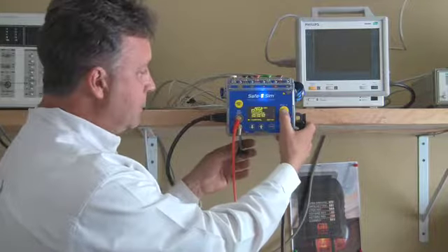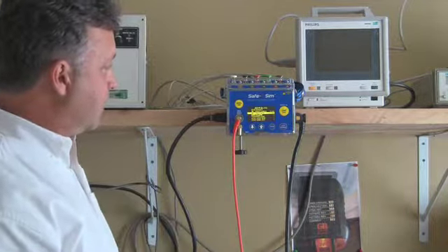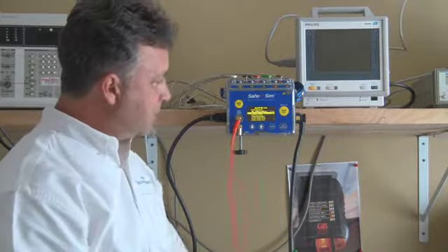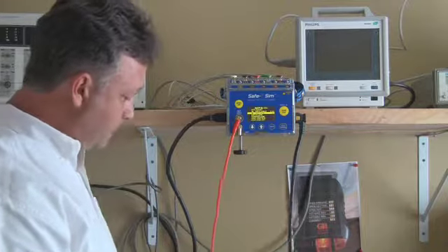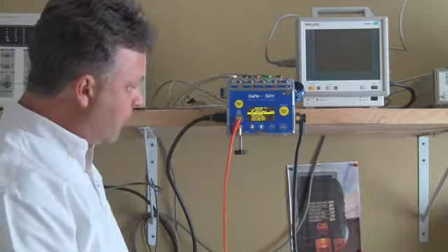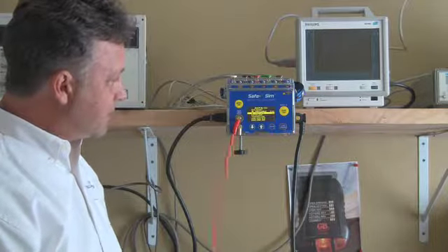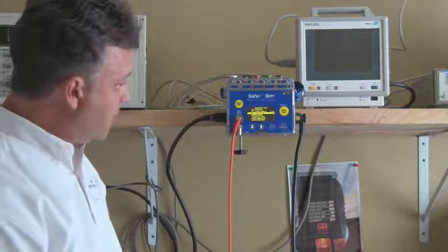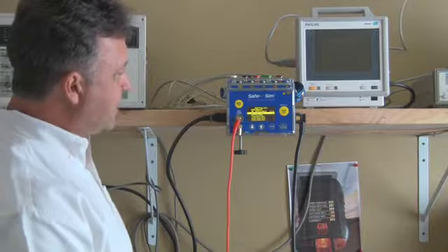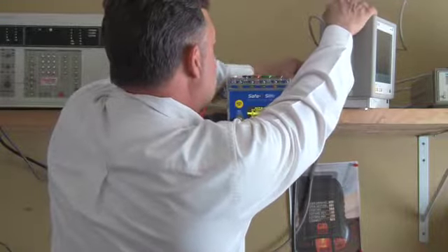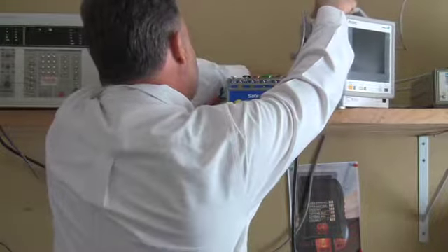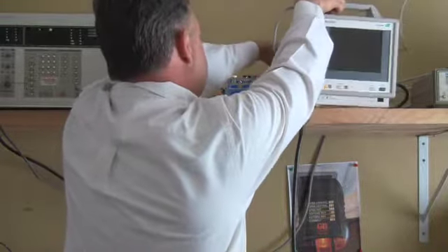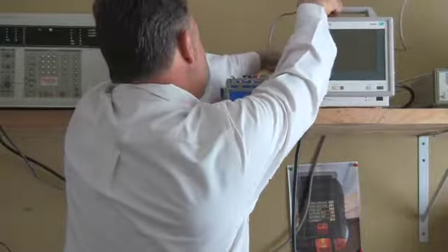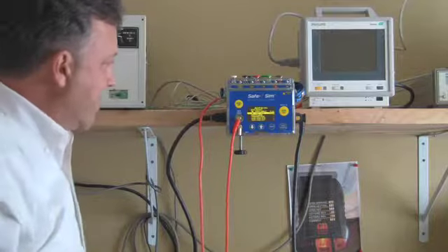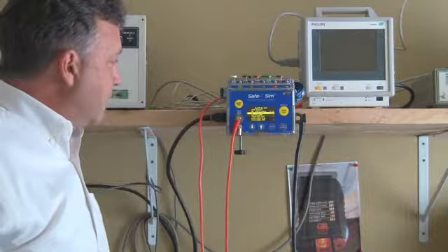So from there, I hit start. It's running a ground test, and notice there's a flashing LED and an audible tone. The audible tone tells you that it is not yet seeing a passing value for the ground test. So the red LED also tells you the same thing. Until it senses that it's got a passing ground resistance, it's going to keep beeping at us and flashing that LED until we get a good value going back to ground. So now it's got a good value and it's moving forward.